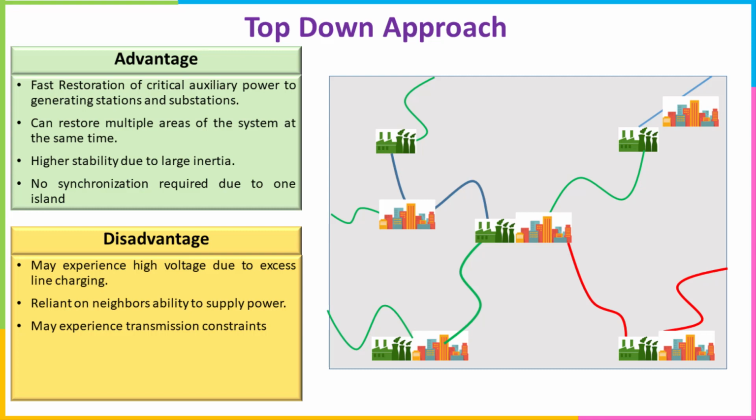In our Indian system, we don't have to worry because all the systems are running at the same frequency. So if one part is left out and one part is blacked out, what we can do is restore from the same system itself, because all of them are running at the same frequency. So the synchronization problem will not be that high. If their frequency is the same, then there will not be any problem in the synchronization. You have to look into the angular aspect rather than the frequency aspect.